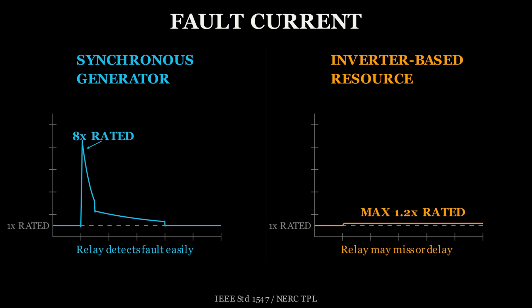Synchronous generators respond immediately. They push current into the fault, 5 to 10 times their normal rated output, for a fraction of a second. This sounds like a problem. It's actually how protection systems work. Protective relays measure current. High current means fault. The relay operates the circuit breaker. The faulted section is isolated in under a second. The rest of the grid continues.